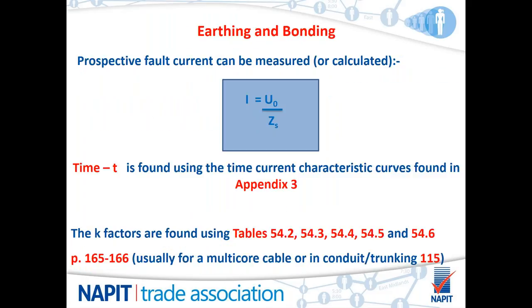So the prospective fault current can either be measured or calculated. Now, the formula in the blue box, essentially, I equals U over ZS. It's a very simple formula. So 230 volts divided by ZS will give you your value. Now, time T is found using the time current characteristic curves found in Appendix 3.